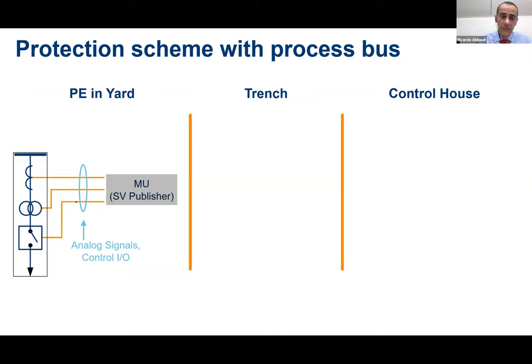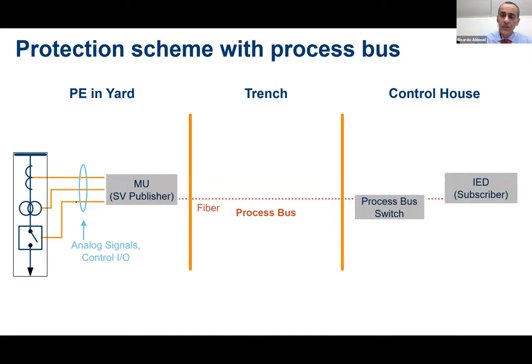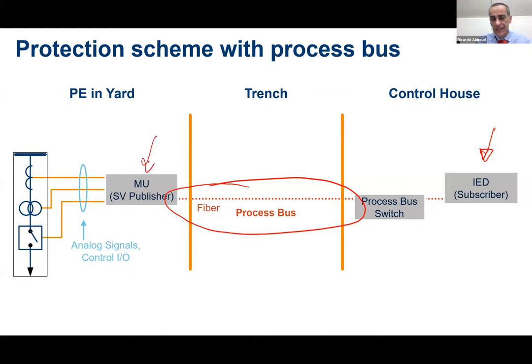So that merging unit will be installed very close to the circuit breaker, and will send the information to the relay, to the intelligent electronic device that is in the control room. We'll send that information through fiber. This is called process bus, okay? So this device will digitize the voltage and currents, and it will send that information to the relay inside the control room through the fiber, using a protocol. That can be sampled values, or we can have different protocols. I mean, 61850 sampled values or different protocols.